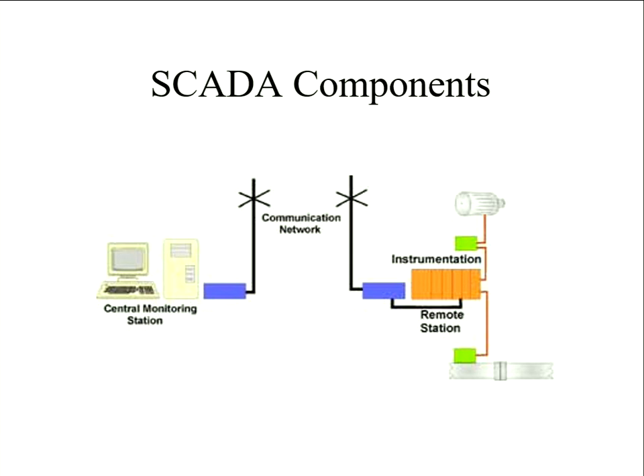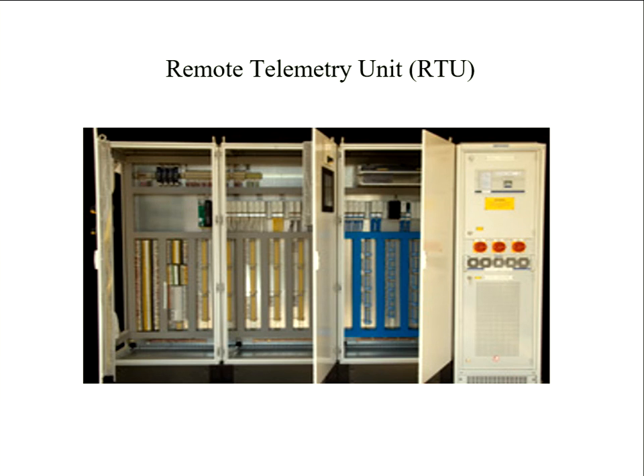That's the sort of thing that people are putting in now, and it's got redundant processing in, so there's a level of redundancy. But the local site has safety overrides or safety lockout. So the safety devices shouldn't depend on the communications loop, because communications can always go down. And in the early days of trying satellites, you could fairly readily track snow through the country as the satellite dishes filled up with snow. But also something like that can interfere with the communication signal. So the safety's got to be devolved down to the site level, and eventually there is a non-electronic form, because what happens if your power goes?